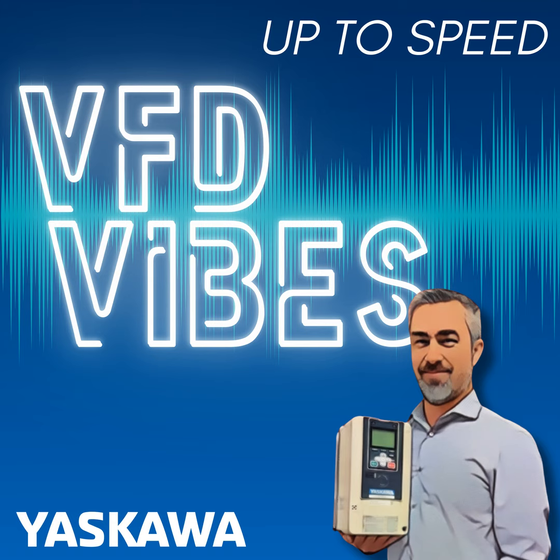To stress that point though, even though we're talking about ghosts in the system when it comes to Ethernet, the same could actually hold true for discrete as well. It's understandable to try to pin some of this on Ethernet at times, but if someone were to drape an analog signal cable in front of that VFD, all of a sudden your speed starts jumping up and down and you're wondering why. So I just wanted to clarify - people always go straight to ghost in the system for Ethernet, but I've seen that even with our good old-fashioned IO.